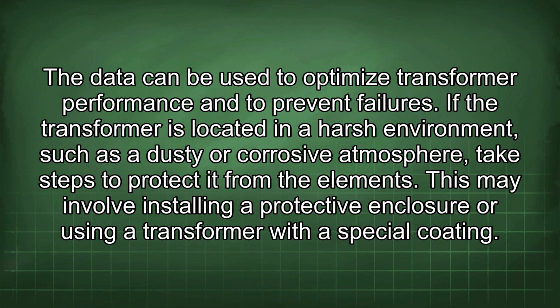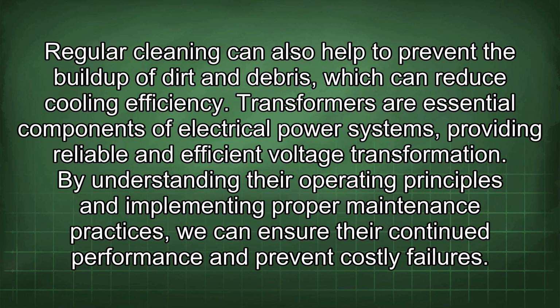If the transformer is located in a harsh environment, such as a dusty or corrosive atmosphere, take steps to protect it from the elements. This may involve installing a protective enclosure or using a transformer with a special coating. Regular cleaning can also help to prevent the buildup of dirt and debris, which can reduce cooling efficiency.